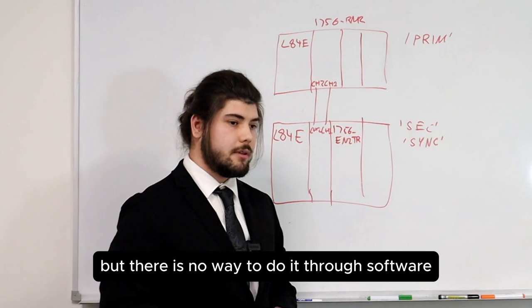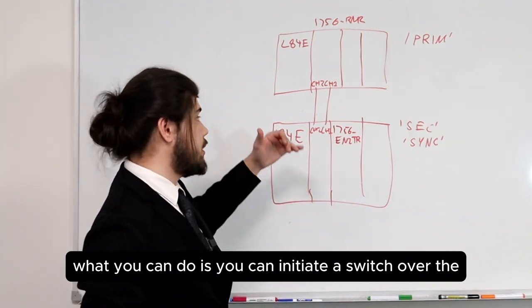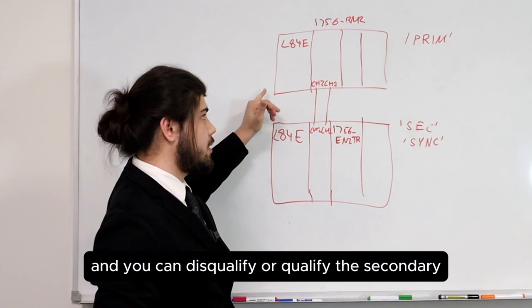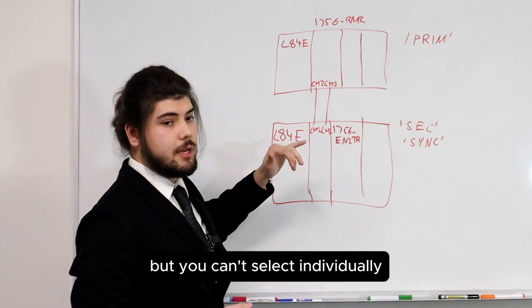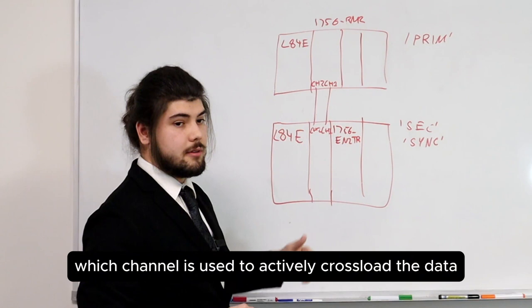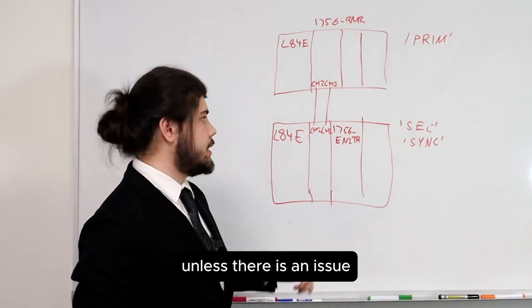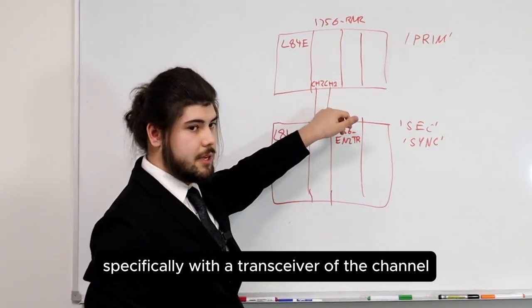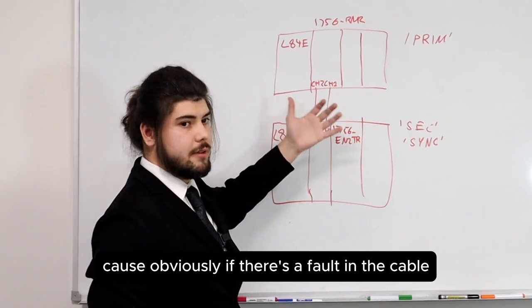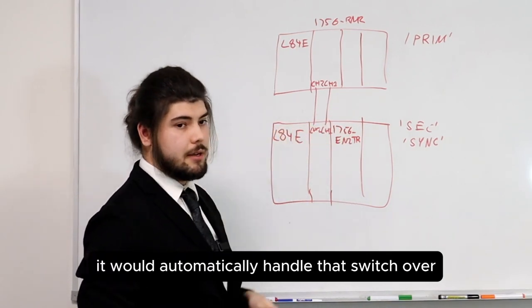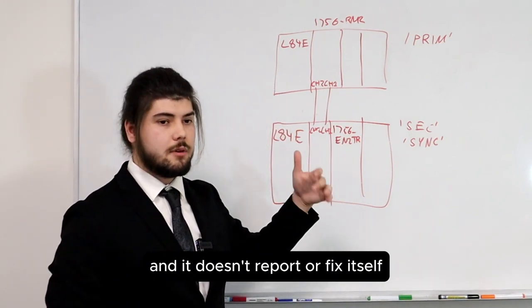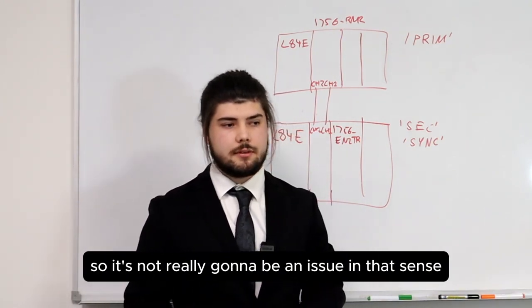There is no way to select the active cross-load channel through software. You can initiate a switchover of the PLCs through the RMCT and disqualify or qualify the secondary, but you can't individually select which channel is used to actively cross-load data. Unless there's an issue specifically with a channel transceiver, that wouldn't be a concern. Obviously if there's a fault in the cable it would automatically handle that switchover, so it would never be in a situation where it's unable to cross-load and doesn't report or fix itself.